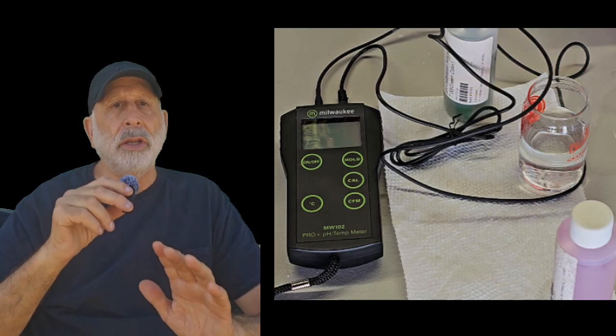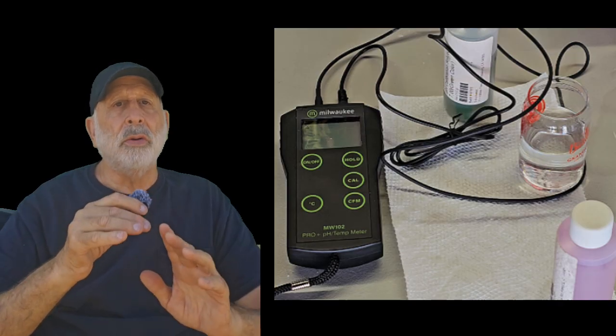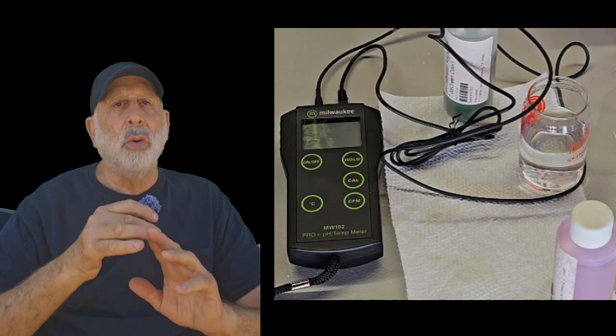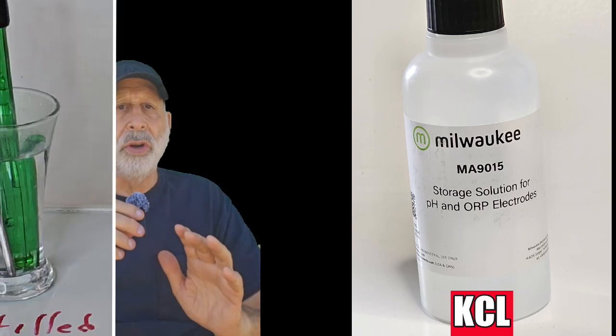It does not always mean the meter is bad. The probe needs minerals to read properly, and pure water doesn't have enough. In those cases, sometimes add a small amount of KCl, which can help stabilize the reading.